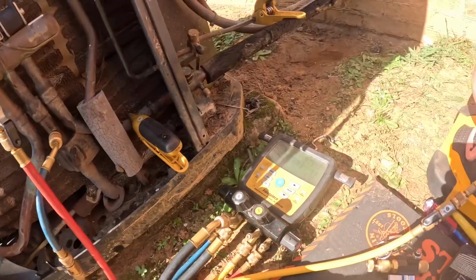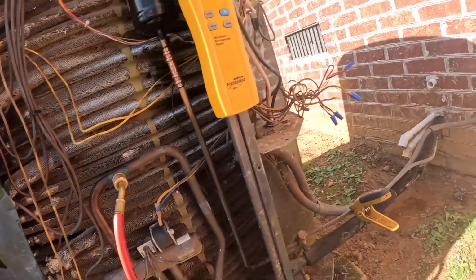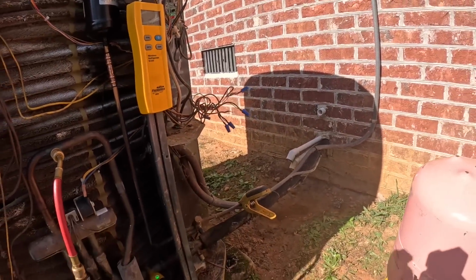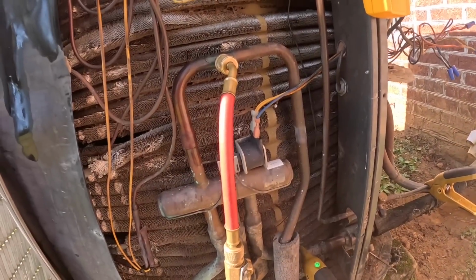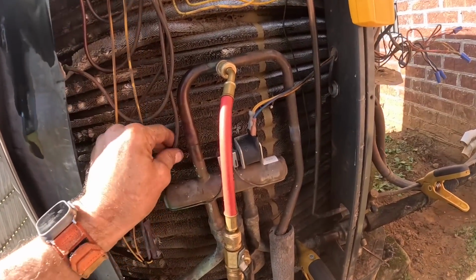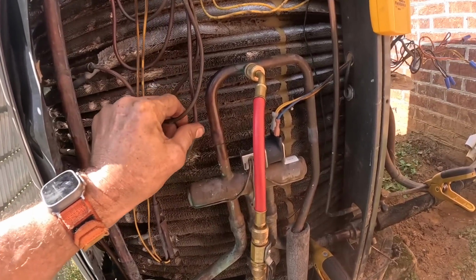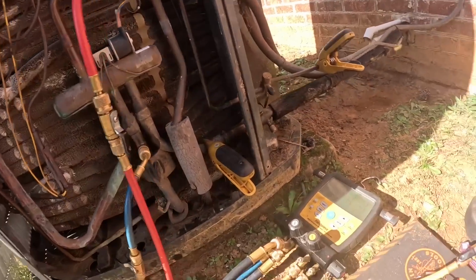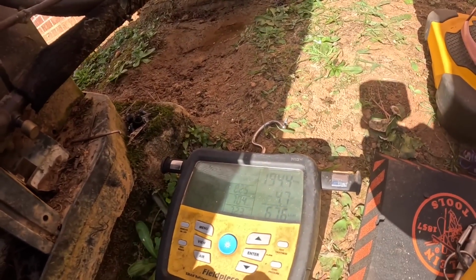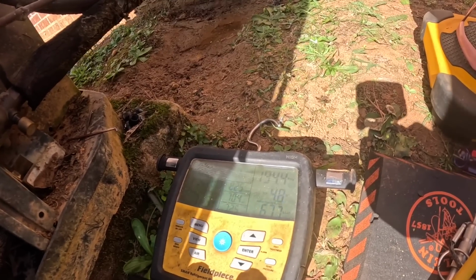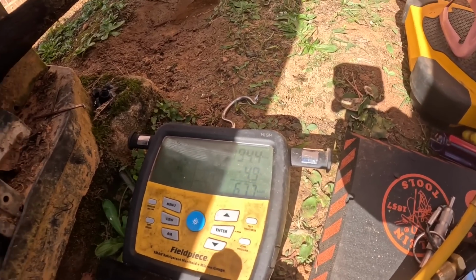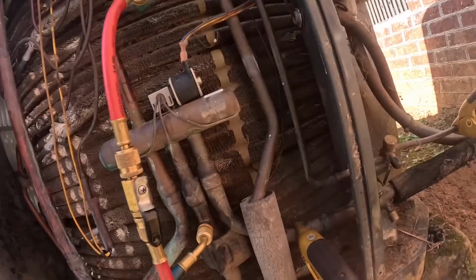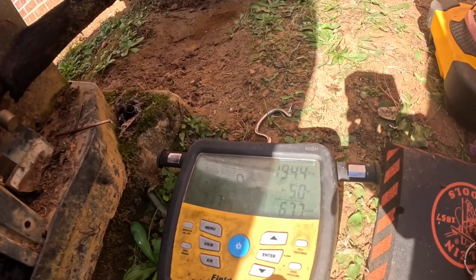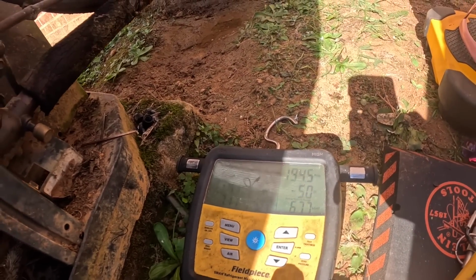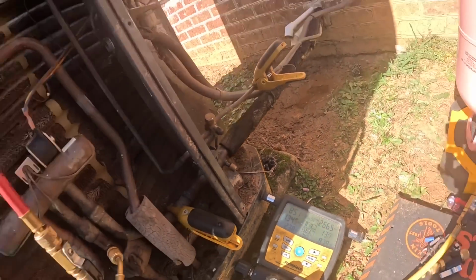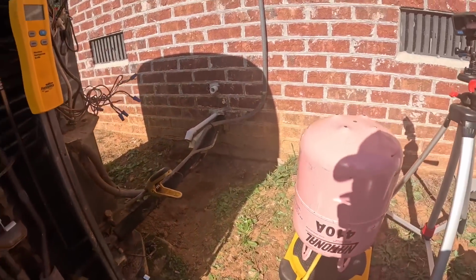Okay, so I stopped charging for a little while and I tried to run it in cooling, and the reversing valve is clicking but it's not shifting. I need a good pressure difference for that to happen, and right now I don't have a pressure difference. Okay, so now I've got a pressure difference, it's running in heat.